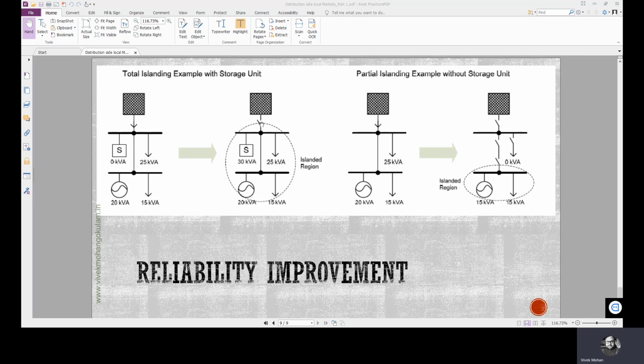Now when the whole system is islanded, this switch is off, so the whole system is islanded. Now this storage device is active. So 30 plus 20 is 50 kVA, right? 50 kVA is there, but this 30 is capacity. Total load is 25 plus 15, which is 40. So 20 is coming from the local generator. 20 can come from this storage device. 30 kVA is the total capacity. So in islanded mode also, generation demand balance is satisfied.